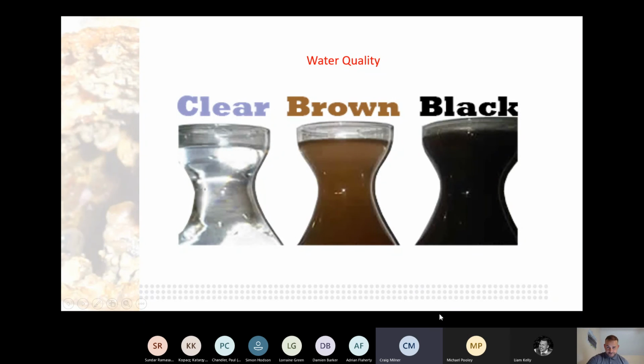This is one where normally, when you're face to face in a room doing the presentation, I've got two bottles, one with brown, one with black, and you ask everybody which they think is the better and the worst water quality. Obviously, the clearer the best. That's what you've got going in. But brown and black, generally everybody picks the black water. Obviously, it looks really dark. It looks nasty. What that is, in fact, is magnetite. So that's a water where there's little oxygen being active, whereas the brown is the more corrosive water quality. So if you're seeing brown water like that, it means there's a lot of oxygen acting in the system, and it's more likely to be causing active corrosion, and it's more of a problem than the black magnetite.